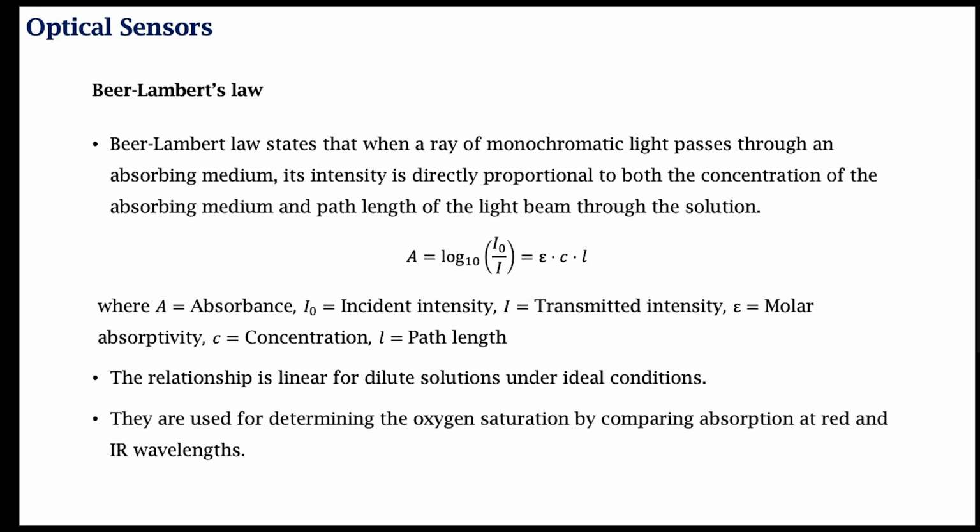During COVID time, this was a device that was used to measure the oxygen saturation in each person, if the person is not able to breathe, if they are having difficulty. This is a non-invasive device that was used to measure oxygen saturation. They were relatively affordable devices. As to whether they were accurate or not, the jury is still out there. But this is the principle of operation.